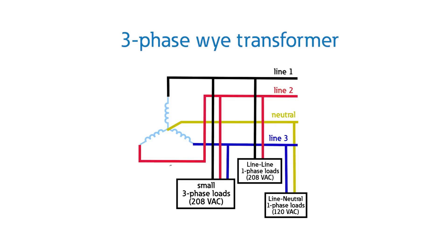Like mentioned before, the advantage of a Y transformer over other three-phase configurations is the neutral connection. Lower power plug loads can be taken from an individual phase to neutral, offering 120-volt single-phase, while higher power loads requiring steady three-phase voltage can be stacked on line-to-line connections for 208 volts.